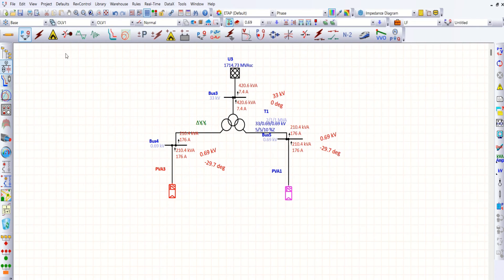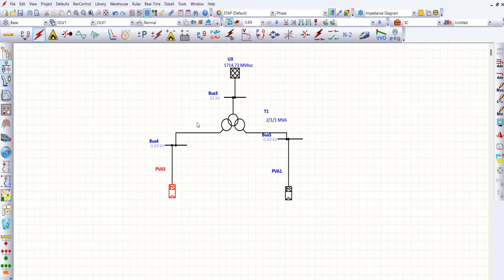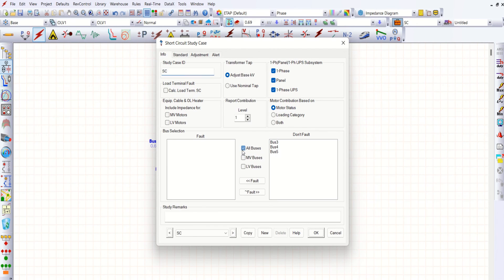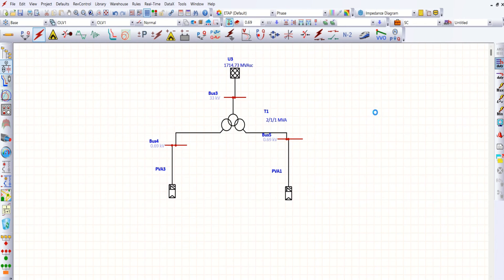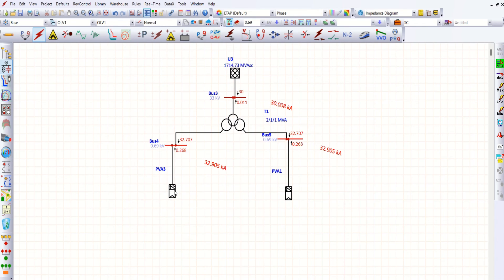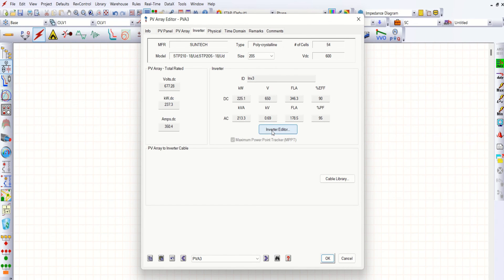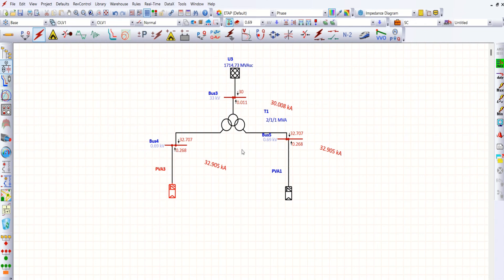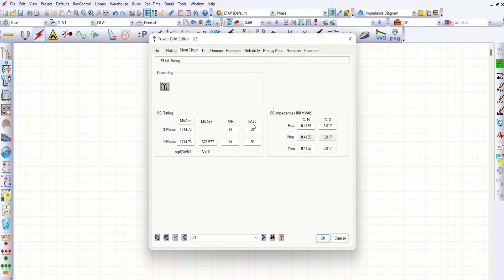Then when we go for short circuit analysis, let me run short circuit here. No bus is faulted by default, so let me make fault on all buses. Now run short circuit. Let's see the short circuit contribution from the PV array — we are getting about 0.268 kA, that is 268 amps. You can see in the inverter short circuit model: we set 150%, and 1.5 times the rated current gives 268 amps. That is what you could see on either case. Short circuit current contribution from upstream is 30 kilo-amps, since we set the short circuit current as 30kA. Put together on bus number 4 — that is the 0.69kV bus — you are getting 32.905 kilo-amps, and the same for the second case as well because a similar rated PV is connected there.